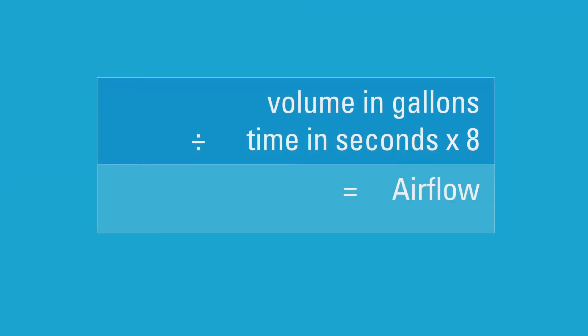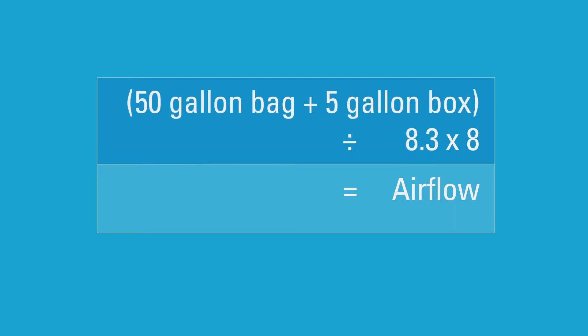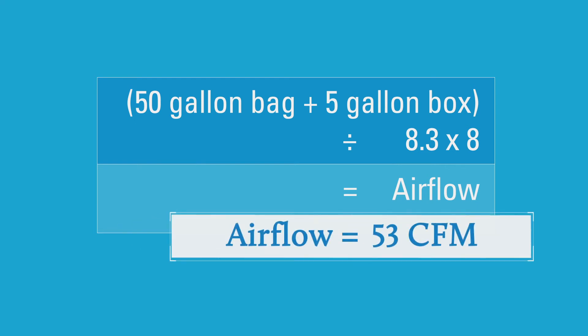Because we know the volume of the bag plus the box is 55 gallons and the elapsed time was 8.3 seconds, we can calculate the airflow in CFM, which gives us 53 CFM.